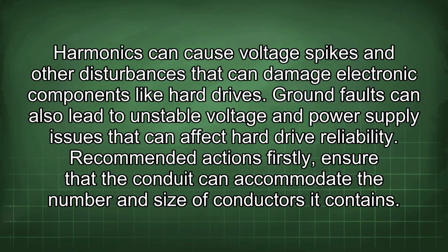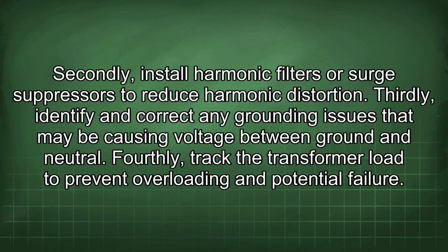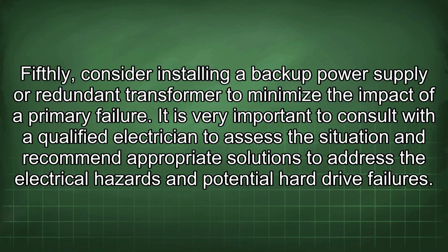Recommended actions: firstly, ensure that the conduit can accommodate the number and size of conductors it contains. Secondly, install harmonic filters or surge suppressors to reduce harmonic distortion. Thirdly, identify and correct any grounding issues that may be causing voltage between ground and neutral. Fourthly, track the transformer load to prevent overloading and potential failure. Fifthly, consider installing a backup power supply or redundant transformer to minimize the impact of a primary failure. It is very important to consult with a qualified electrician to assess the situation and recommend appropriate solutions to address the electrical hazards and potential hard drive failures.